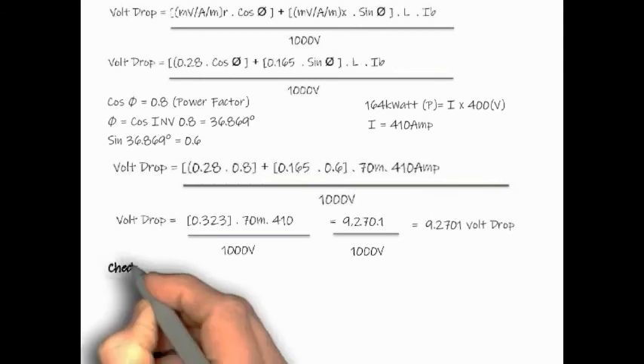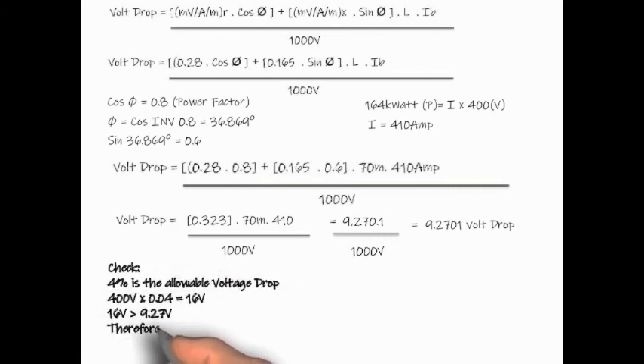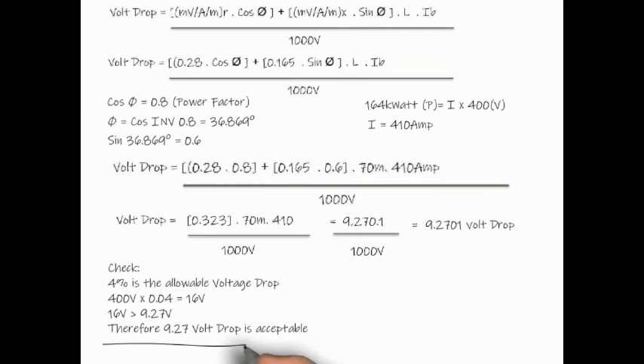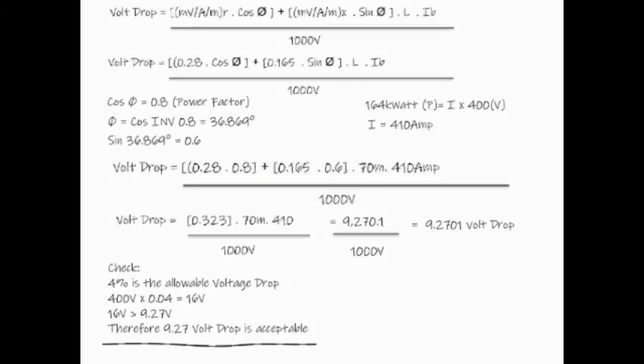So this is the voltage drop value that you have calculated. Now, how do I know whether this fulfilled the allowance for voltage drop? So I will use 400 volts multiplied by 0.04. This will give me 16 volts. So 16 volts is higher than 9.27 volts which I've calculated. Therefore, this value of voltage drop is acceptable.